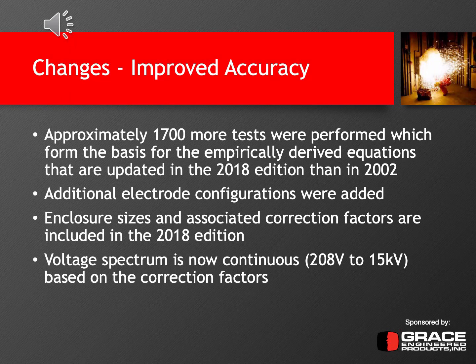So another major change that occurred in the 2018 edition is basically the improved accuracy of the model, and that's based off of the approximate 1,700 additional tests that were performed between 2002 and 2018, plus the 300 original, for a total of about 2,000 test points that form the basis of these newly derived empirical equations that have since been updated from the 2002 to the 2018 edition of the standard.